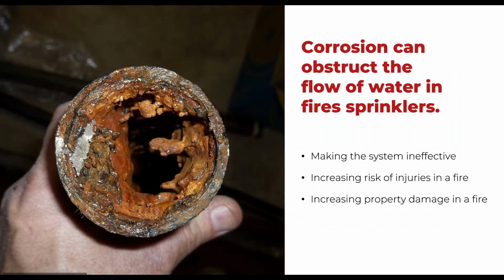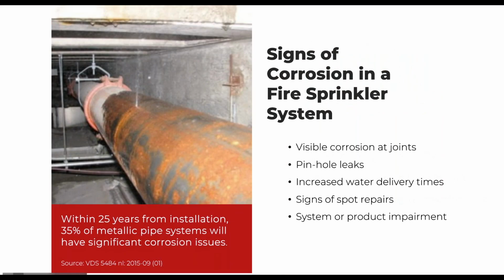What we're concerned about in the fire sprinkler industry is that corrosion can impair the life safety system. It could reduce the inside diameter, like you see in the picture, where you've got this great reduction in the diameter of the flow path of the pipe. It could cause catastrophic failure of the piping. You could have joints fail. And again, you could also have life safety issues where the water can't physically get to the sprinkler heads to put the fire out. So corrosion is an extremely important topic in the fire sprinkler industry. It's kind of been our number one topic for the last several years, on how to deal with corrosion and the effects corrosion has.